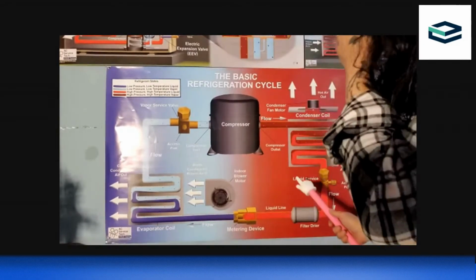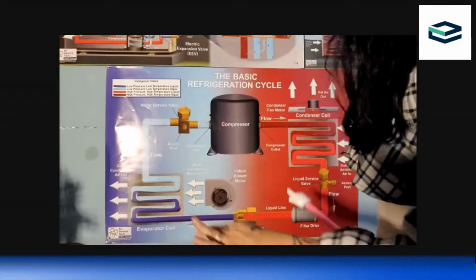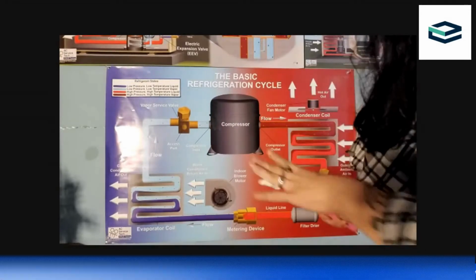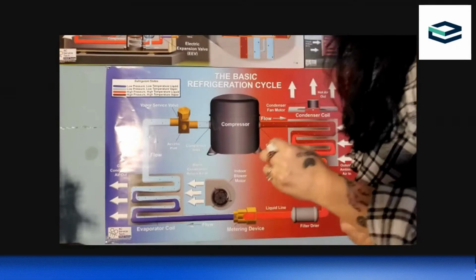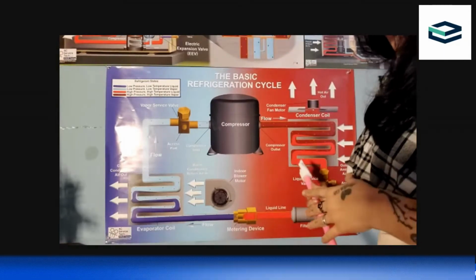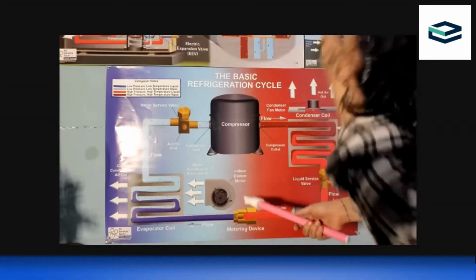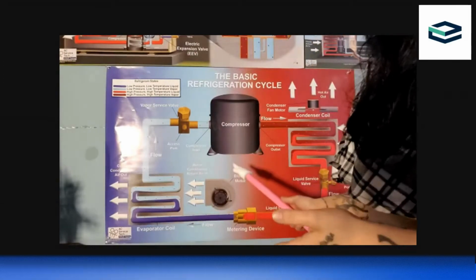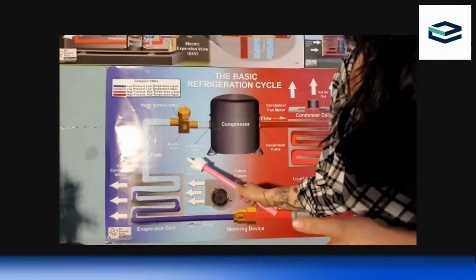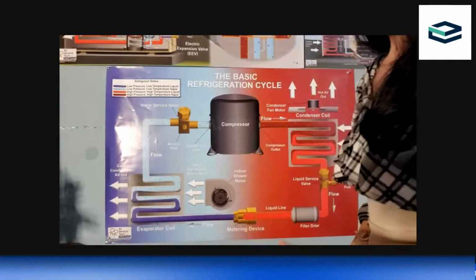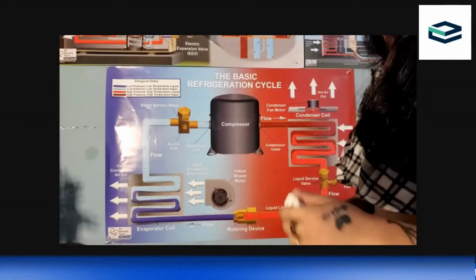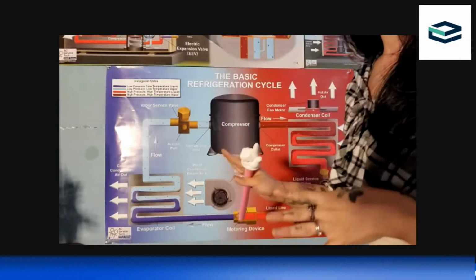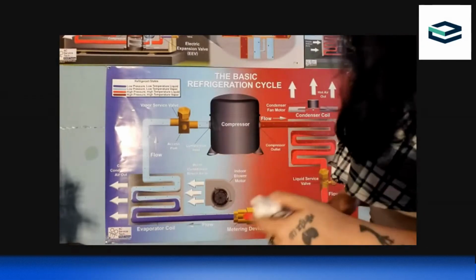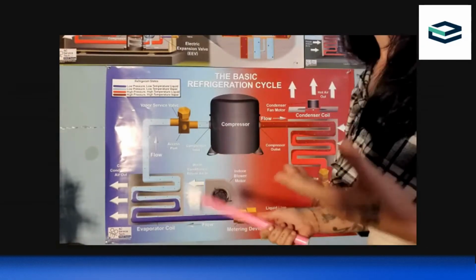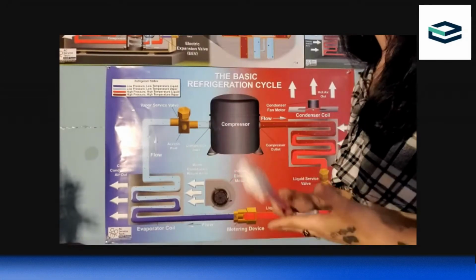So if you've got a normally working system, you want the liquid saturation to be somewhere, for 410A, somewhere over 100. You want it to be hot on that side. If you have a normally working system, your vapor saturation should be relatively low. Not too low. I like to see 30 to 50. 40 is my bread and butter. That's my sweet spot. But there are lots of reasons that it wouldn't be dead on. So it is kind of a spectrum.